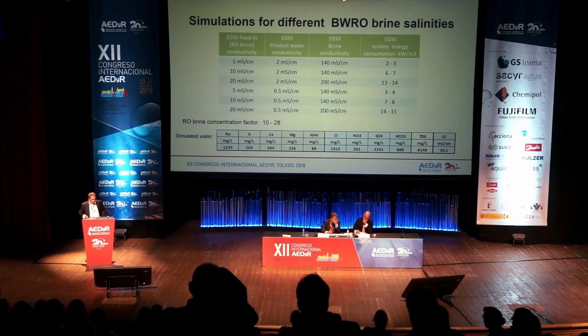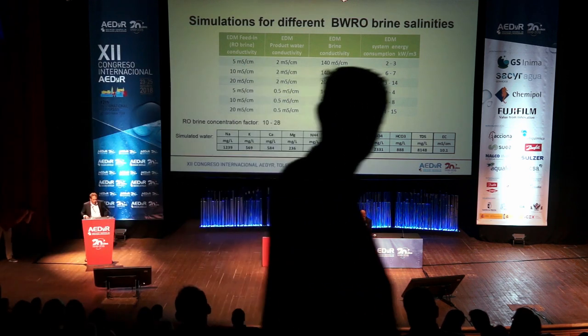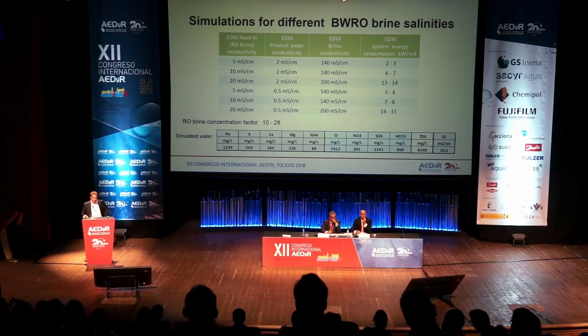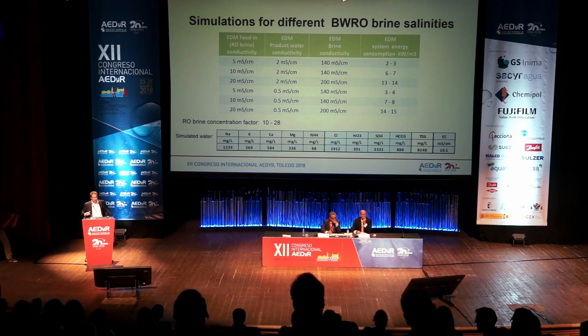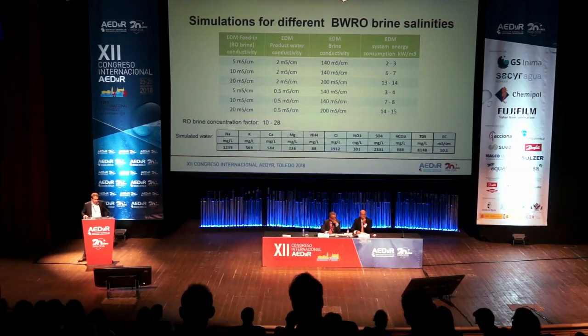We made two different simulations: one targeting product water of 2 millisiemens per centimeter, and another targeting 0.5 millisiemens — potable water level. Depending on the feed stream starting point — 5, 10, or 20 millisiemens — the total energy required is between 2 and 15 kilowatt-hours per cubic meter for the different settings. The brine concentration factor is between 10 and 28.